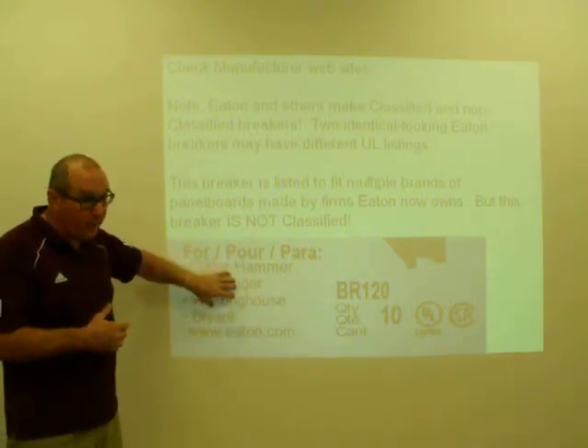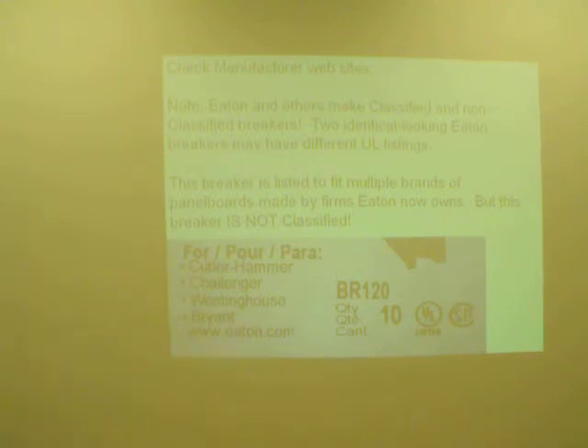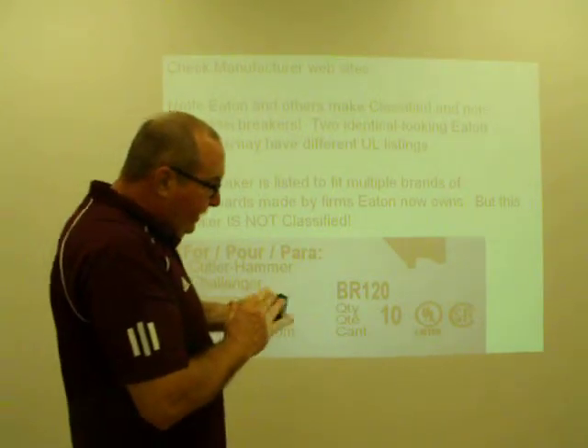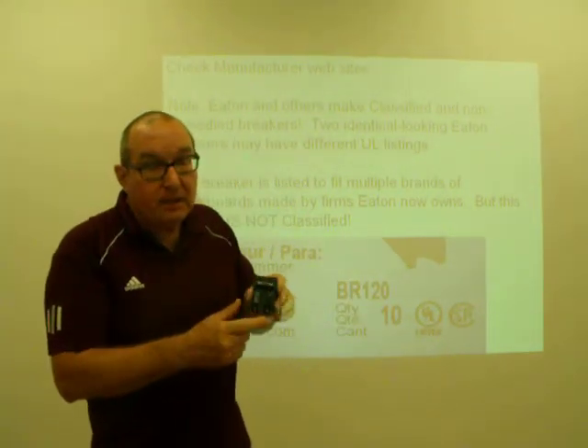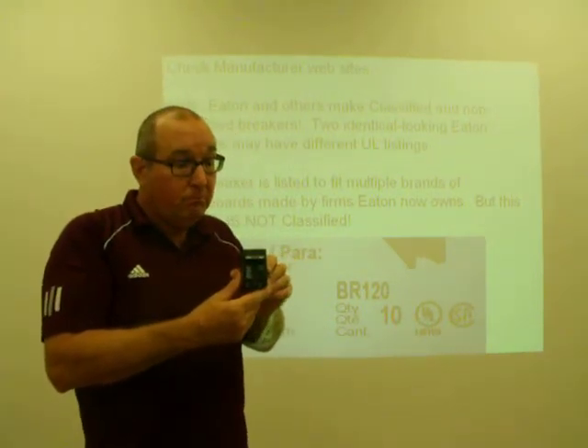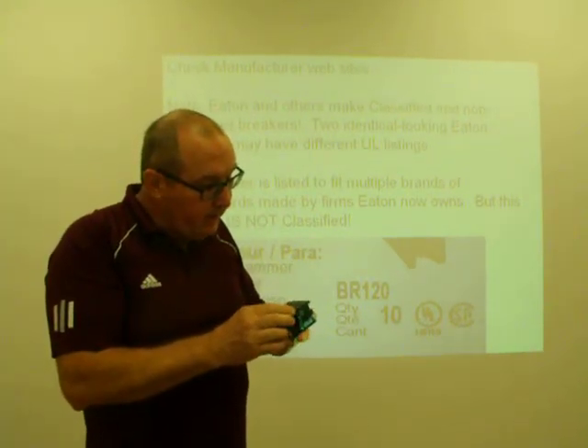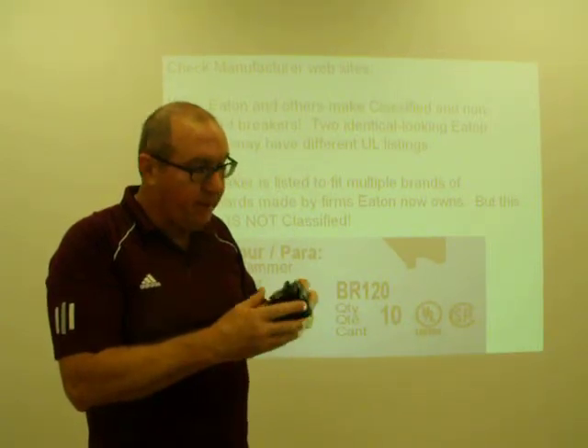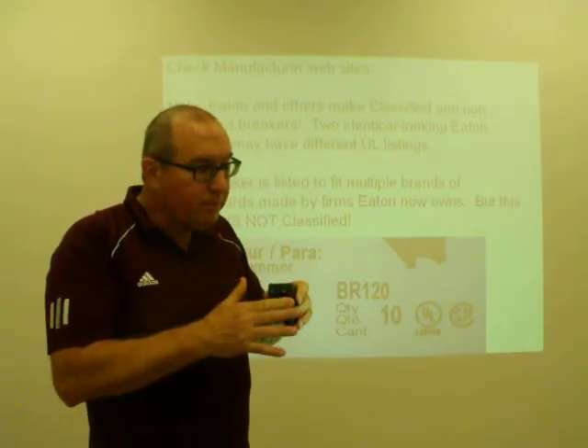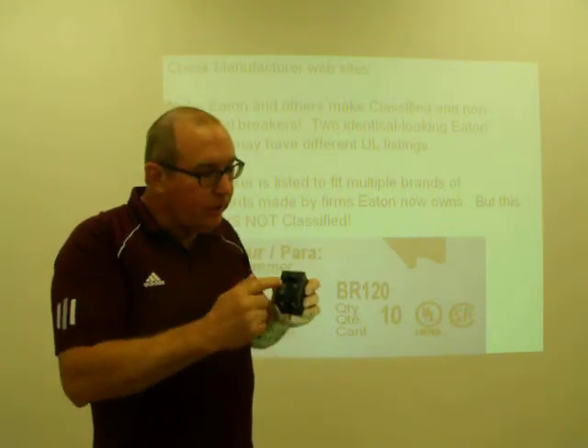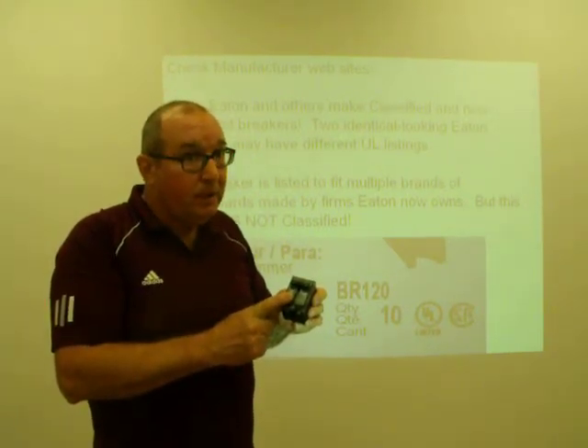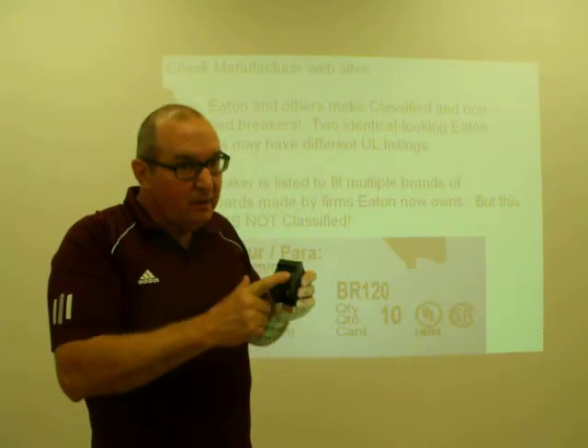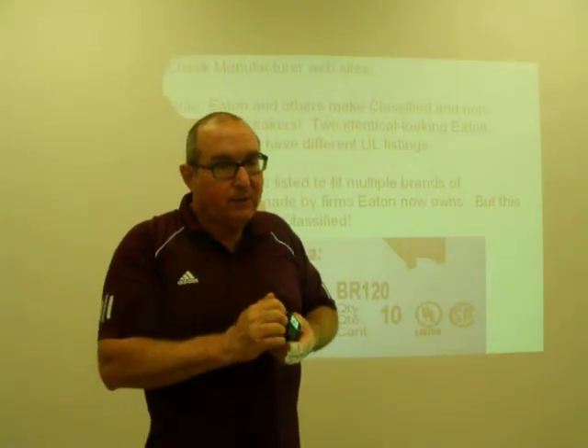In fact, if you look at this breaker, and I have a couple of Eaton non-classified breakers here, you will see there is nothing on this breaker to indicate that it is for classified use. There's nothing on this breaker that tells you that you can use this for replacement in somebody else's brand of panel. So this breaker may be identical to a 2-pole 20 classified Eaton breaker, but because of the way it's labeled and listed, they're not interchangeable if you're putting them in a non-Eaton panel board.